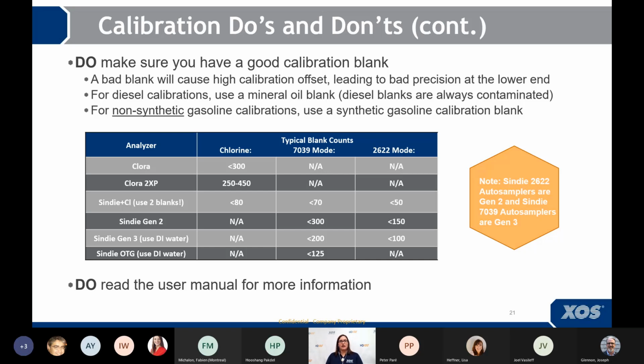And then if you're using a gasoline calibration, I'm not talking about the synthetic gasoline, I'm talking about a non-synthetic gasoline calibration, those will often come with a blank as well. And what often happens is those are not blank either. Those are contaminated. So you want to toss that out and use a synthetic gasoline calibration blank, something like isooctane or an isooctane toluene blend.